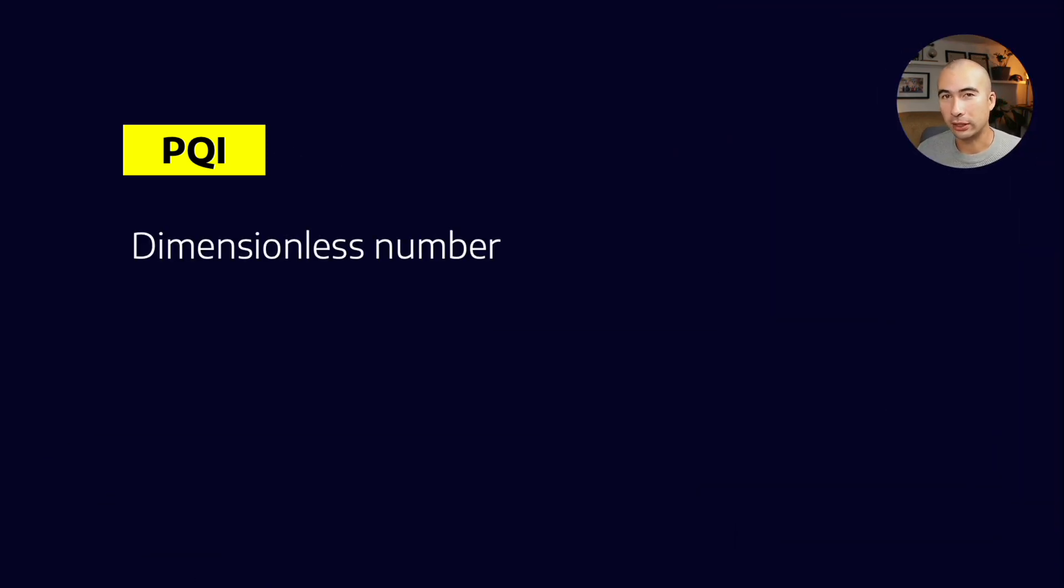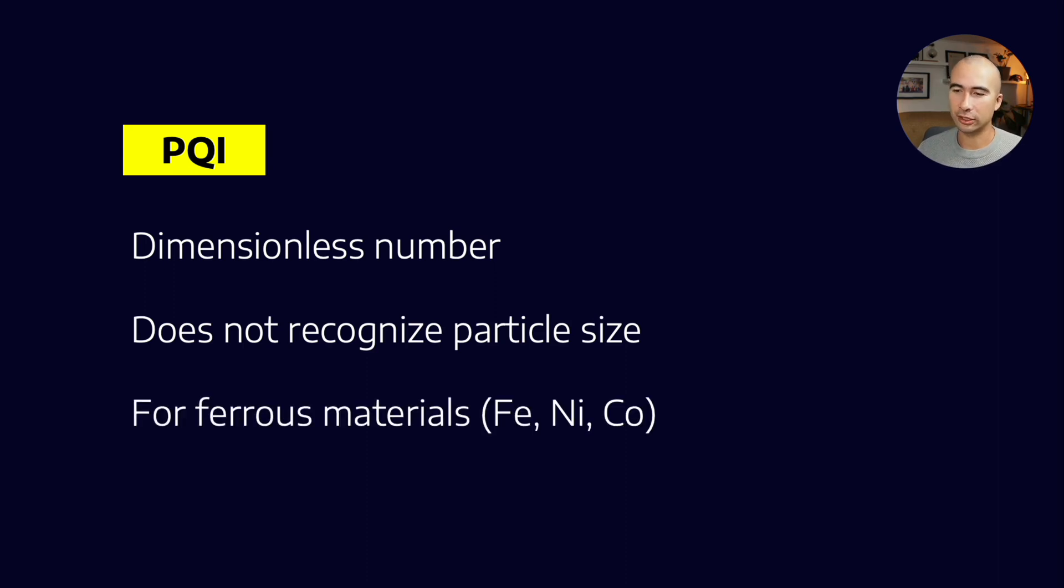So the PQ index, the things to know is that it's a dimensionless number, it doesn't recognize particle size, and it's a test specifically for ferrous metals: iron, nickel, and cobalt. Fortunately, we don't see much nickel and cobalt in either our formulations or in our equipment. So generally, what we say is that the PQ is just a proxy for the ferrous content, that is the iron content of an oil sample.